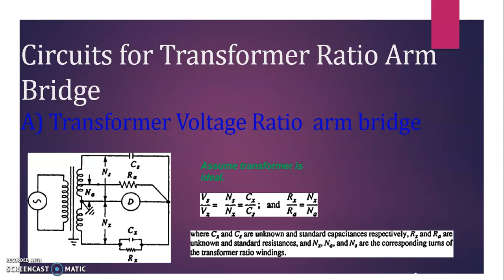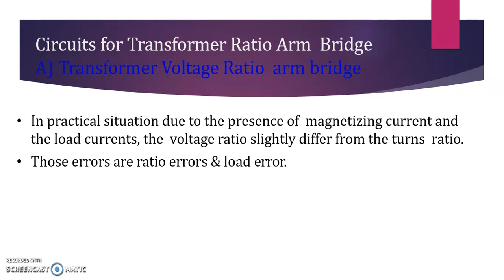Now, in the practical transformers, the voltage ratio slightly differs from the turns ratio. Now, this is obviously due to the no load magnetizing current and also some effects due to the load current also. Therefore, the balance conditions shown in the above equation can give you errors while calculation. Now, these errors are again classified as ratio and loading errors, and they are determined separately and compensated for in the construction. You will have to make some compensation in the circuit for changing these values.